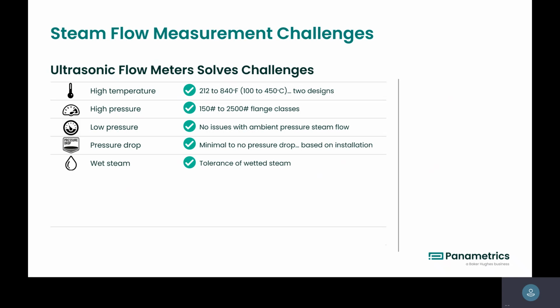Wet steam. Again, we're tolerant of wet steam. We actually can show some diagnostics. We'll see some of the gain and how steady the gain measurement is. So we can handle some of that wetness. Like I said, we're measuring a two-phase system. No, we want to keep it as close to the gas phase as possible. Well, early on, you'll see some of the diagnostics where we can tell, okay, something's going on there. It's not just the gas. We're seeing some difference. And that's what's important in the ultrasonic, to provide some of these diagnostics that are so important.